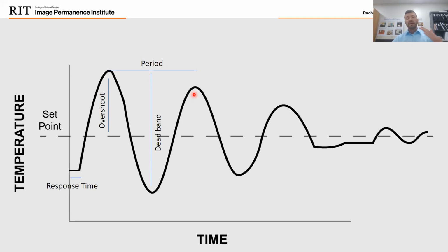What they found was, even though they bumped the temperature back down to 68, the number of people in their galleries was still keeping the temperature at 70, 71, 72 degrees, just the amount of people within that space, the body heat from individuals. And there was a slight moisture uptick from the attendance as well. Not major, but occupancy in a space includes both heat and some moisture.